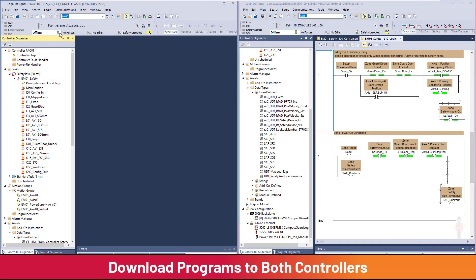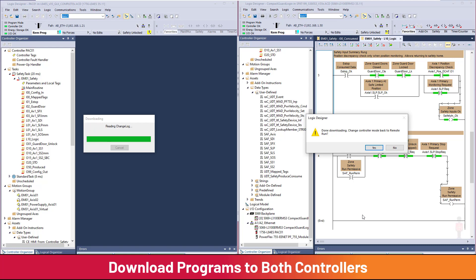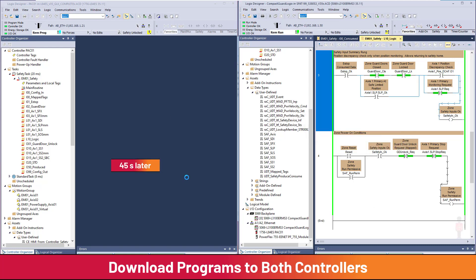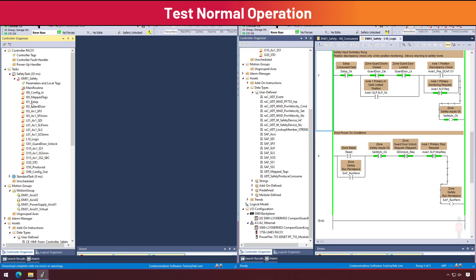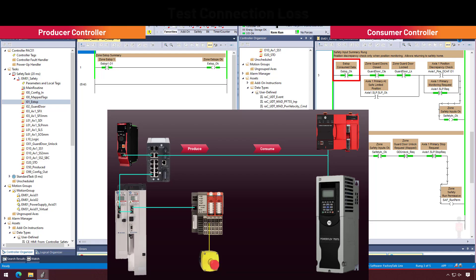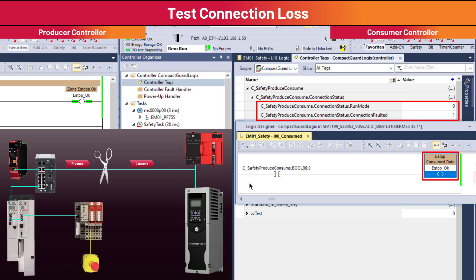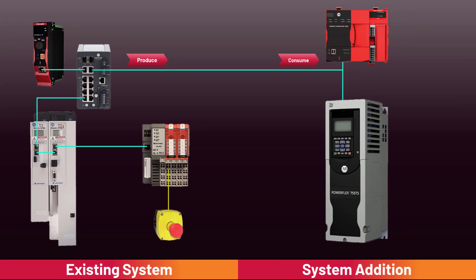Download programs and test. Verify the E-stop OK in the consuming controller goes off when the E-stop is pressed. Break the Ethernet connection between controllers and validate that the consumed E-stop OK goes off and both Run Mode and Connection Faulted transition properly. The system is now functioning with a produce/consume connection between the GuardLogix and the Compact GuardLogix controller.